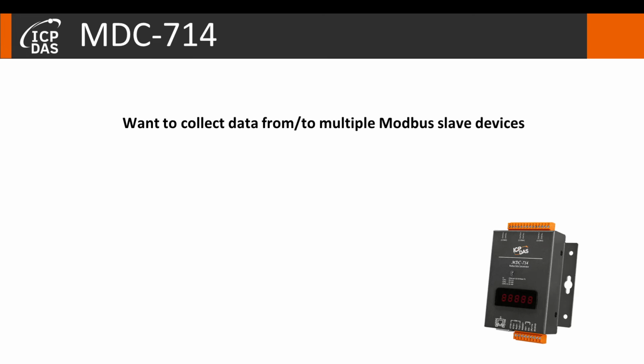So when do you need the data concentrator? When you want to collect data from or to multiple Modbus slave devices, but you suffer from the low baud rate, so the whole process is really time consuming. Then MDC714 will be your best choice. It can help you collect the data immediately.